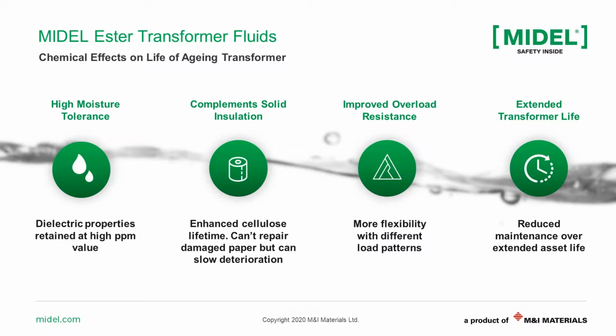From another point of view, a higher operation temperature is possible, as Steve mentioned earlier. Due to the higher fire point and higher flash point, we are able to increase the operation temperature of these transformers. In other words, there is a higher chance of getting better overload capability or overload resistance in this case.